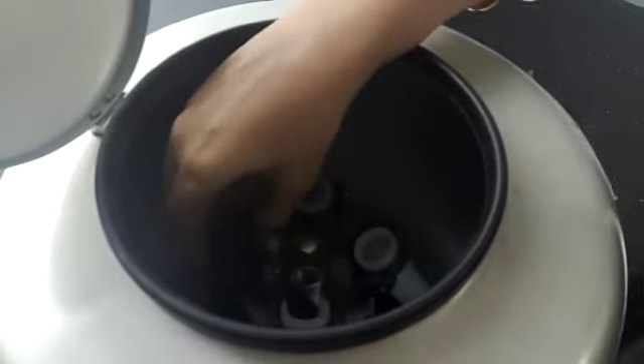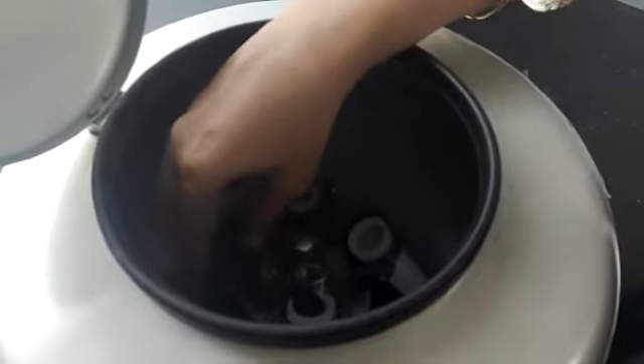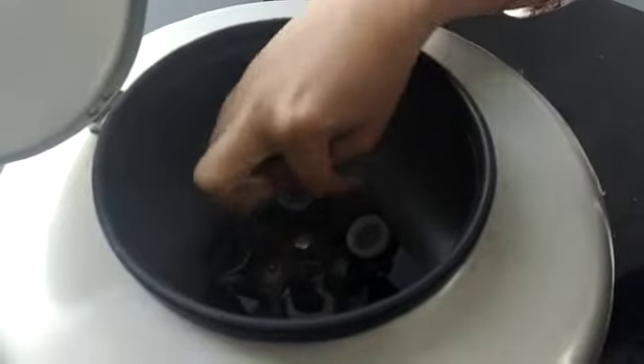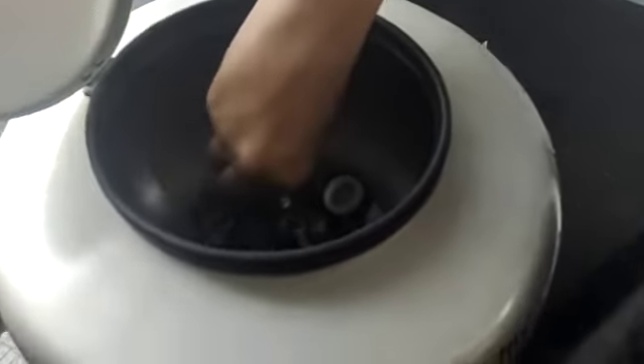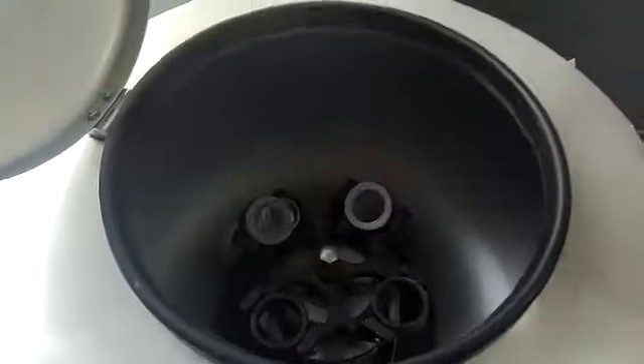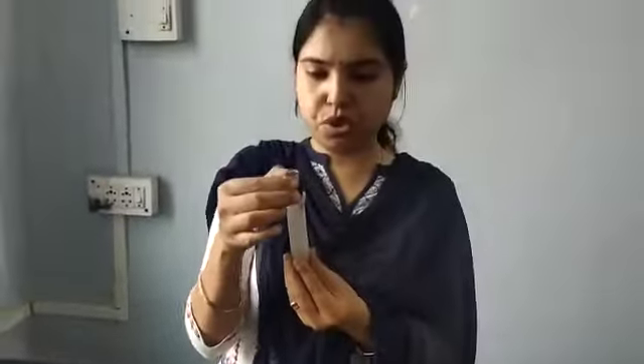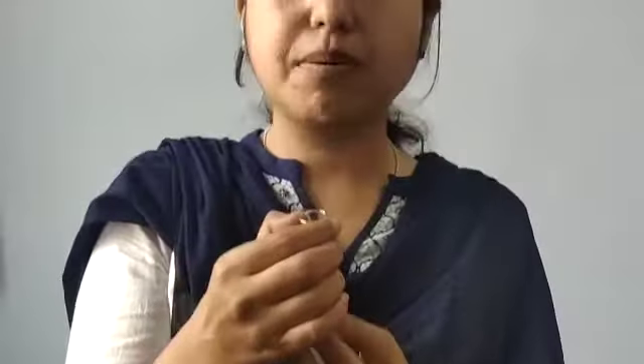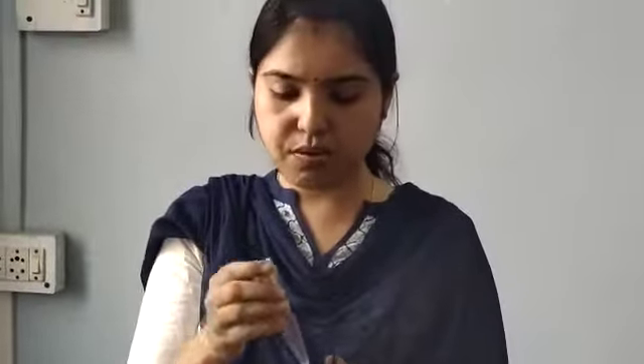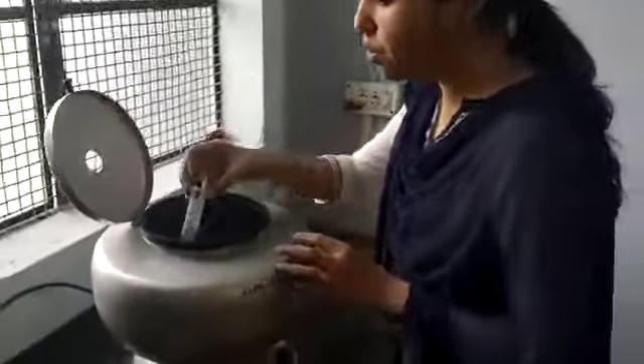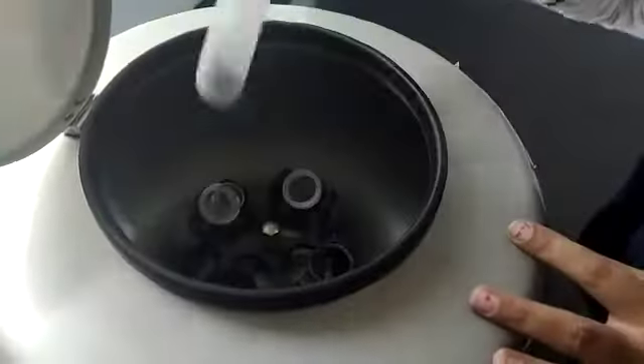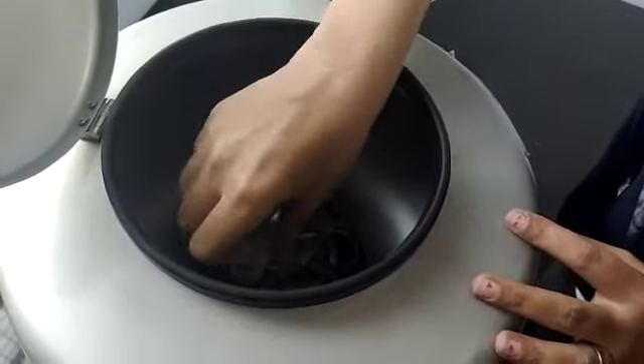This is the ring, which is made of and coated with chrome. This rotor is made up of aluminium alloy. This is called the bucket, which holds the centrifuge tube. The centrifuge tube has a capacity of 15 ml and it can hold up to 23 grams of liquid. This is a rubber insert. Whenever we are using the centrifuge, we need to insert this rubber insert so that the centrifuge tubes are held firmly in the buckets. After this, we have to place the buckets into these rings of the rotor.